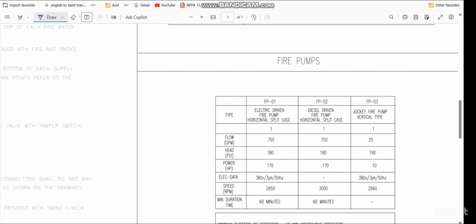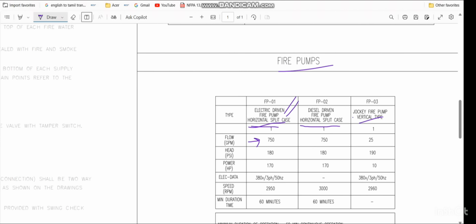The next one is the fire pump for this project. We have used the electric driven fire pump, horizontal split case, and the diesel pump also horizontal split case, and the jockey pump is a vertical type. You know, there are 4 types of fire pump. In this project we have used the horizontal split case pump, and the capacity is 750 GPM. Both this one 750 GPM and the jockey pump 25 GPM, and head we have given 180, and jockey pump 10 meter head higher, 10 psi higher, 190.